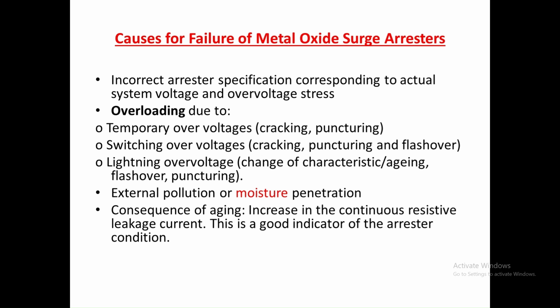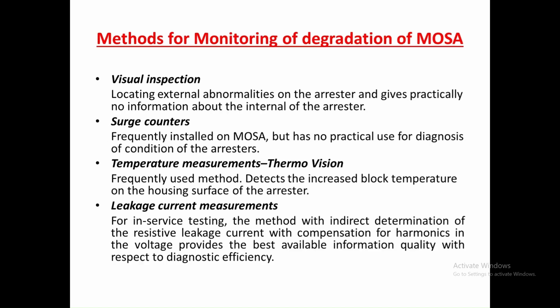We need to again monitor the status of the surge arrestor by following these four methods: through visual inspection, through counters, through thermovision scanning camera, and doing the LCM, that is the leakage current measurement, in between.